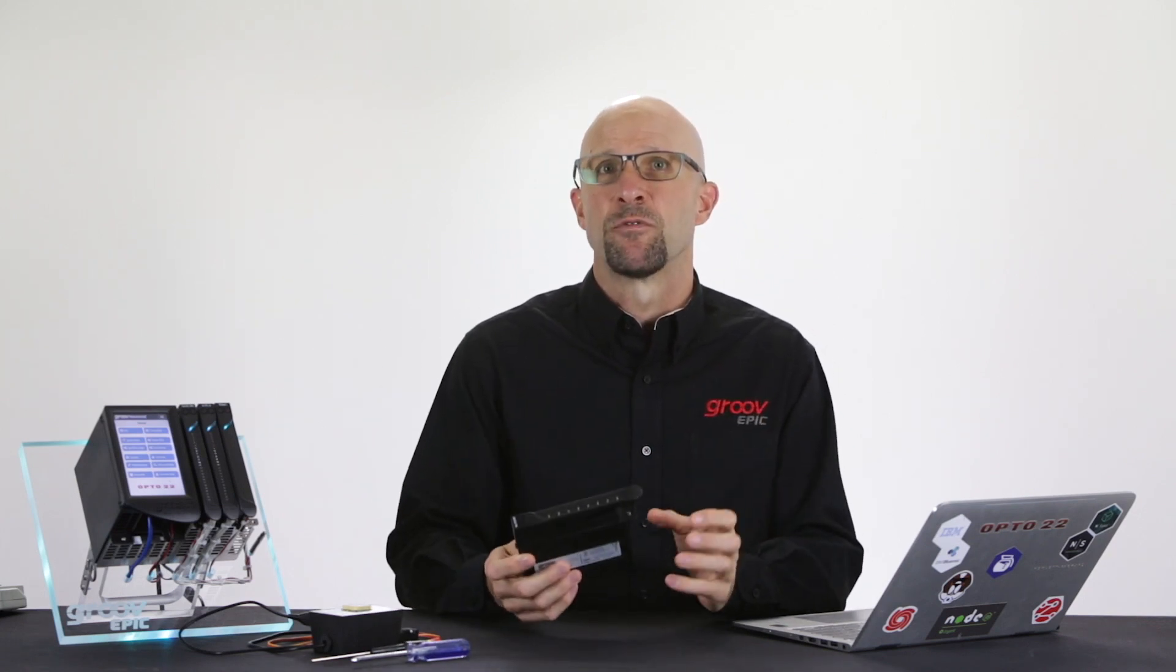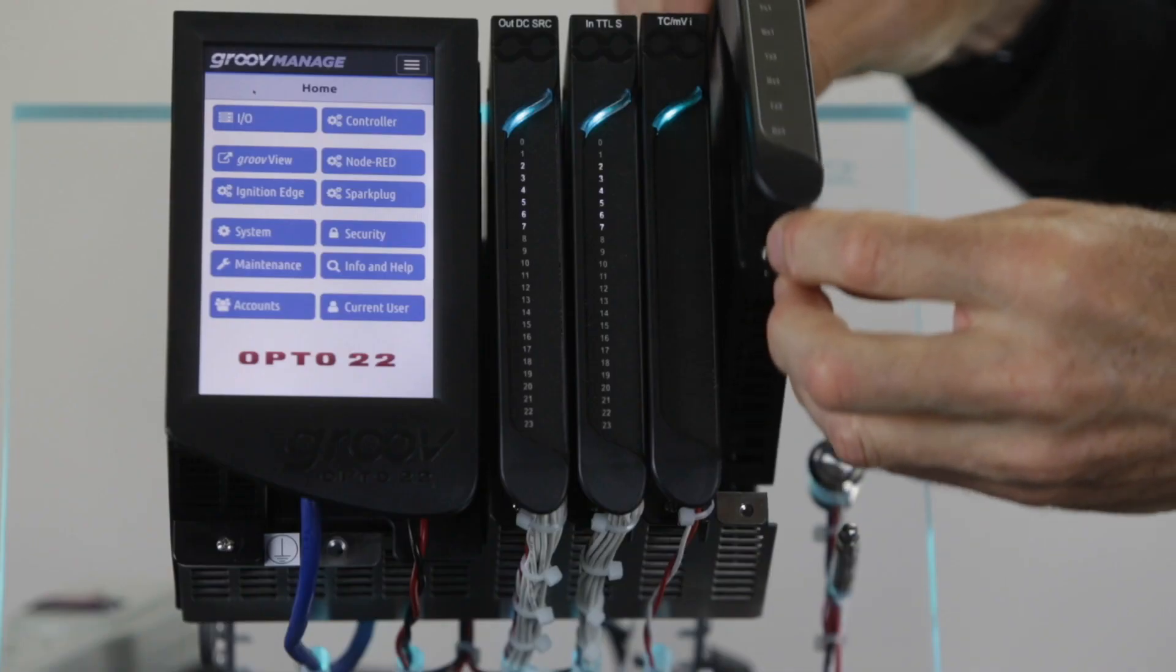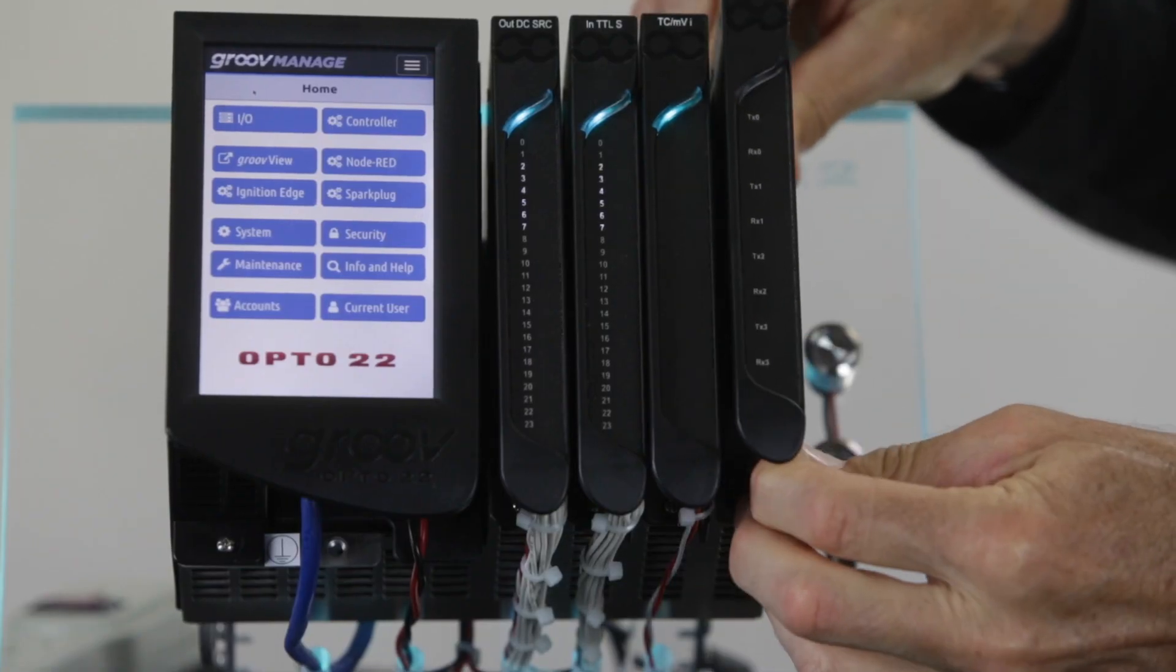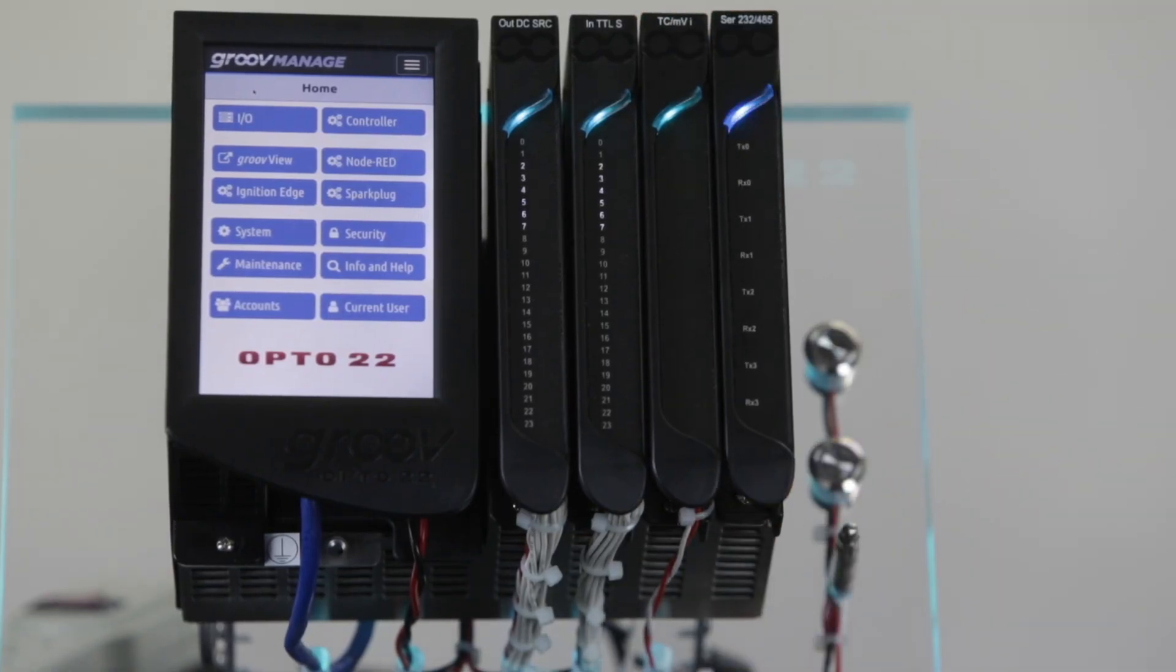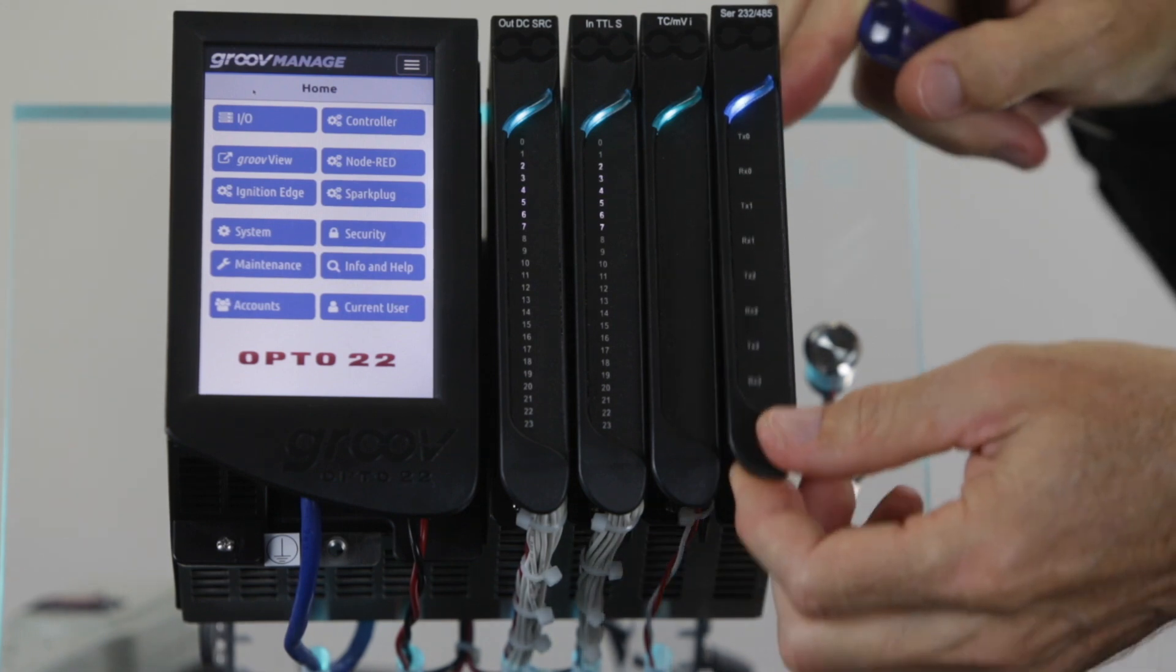First, start by installing the groov EPIC serial I/O module on the rack. Note that it must be placed somewhere in the first four positions. Ensure that the module is fully seated and secure the front retaining screw.